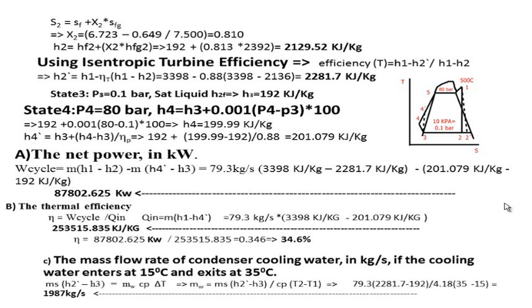Finally, to find the mass flow rate of cooling water that we have to use to cool the steam down and condense it, we should use the heat balance equation. The amount of heat that leaves from the steam to the water is taken by the water to change its temperature from 15 to 35. Using this heat balance, the mass flow rate of cooling water will be calculated as 1987 kilograms per second.